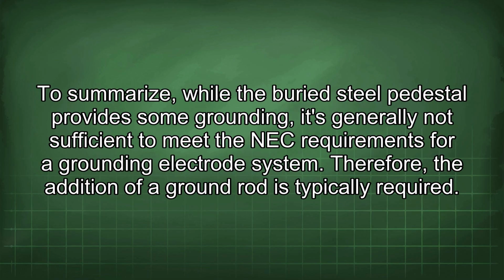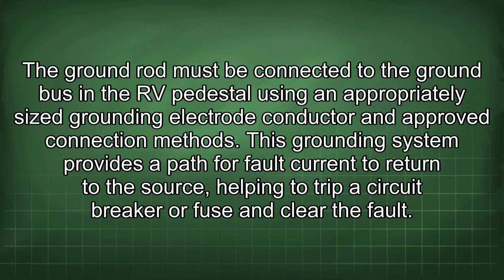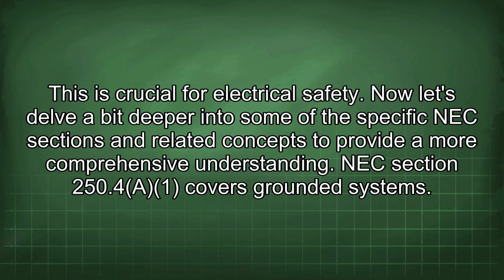To summarize, while the buried steel pedestal provides some grounding, it's generally not sufficient to meet the NEC requirements for a grounding electrode system. Therefore, the addition of a ground rod is typically required. The ground rod must be connected to the ground bus in the RV pedestal using an appropriately sized grounding electrode conductor and approved connection methods. This grounding system provides a path for fault current to return to the source, helping to trip a circuit breaker or fuse and clear the fault. This is crucial for electrical safety.